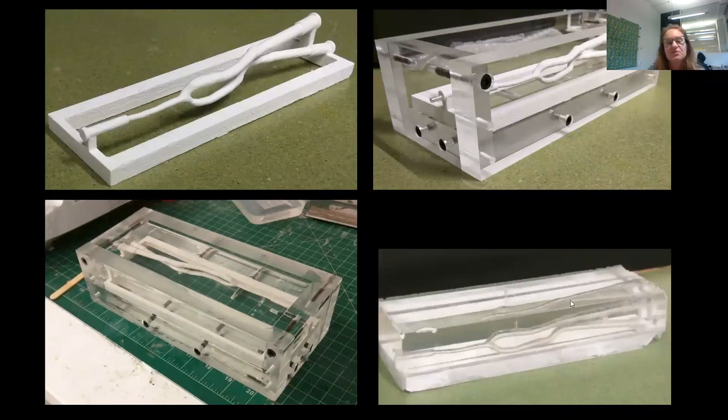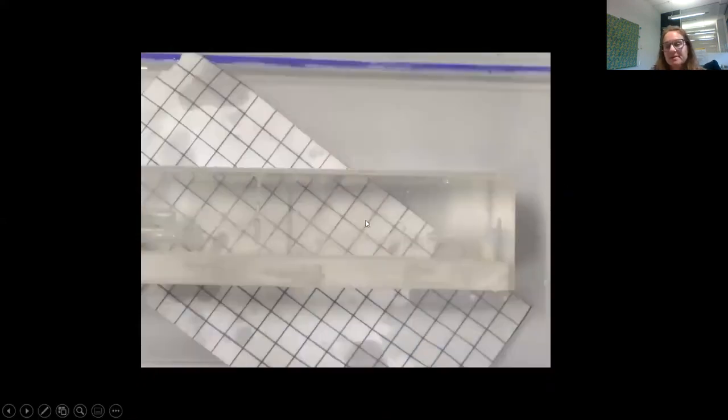So what we do now is we 3D print the fistulas. This is the plaster one. We've also done them in wax and PVA and PVB, and we're looking at a number of different materials. What we then do is we make, in this case, a very over-engineered box, and we pour in PDMS, which is a type of silicon, and then we dissolve out the 3D print. And so we're left with this really nice, pretty accurate patient-specific geometry, which is optically clear. And because it's silicon, we don't need to use sodium iodide, which is pretty horrible to work with. We just need to use sodium chloride and some glycerol, and then we can make these ones disappear.